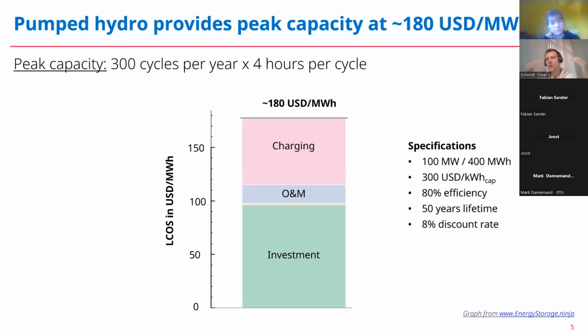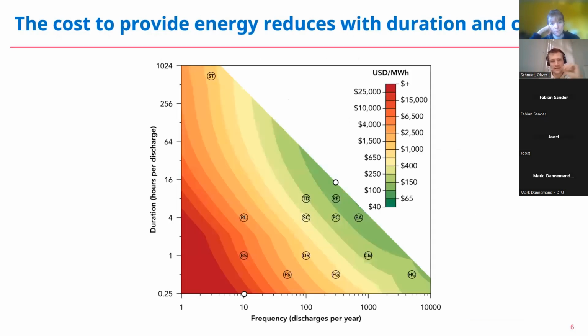Now, I would like to do this for all possible applications there are, and I'm going to do that on the next slide. On the next slide, you can see on the y-axis the discharge duration of any possible application, ranging from below 1 hour up to 1,000 hours. And on the x-axis, the annual cycles of any possible application, ranging from 1 cycle per year up to 10,000 cycles a year. So if we orient ourselves again, we were looking at peak capacity on the slide before, which had 4 hours discharge duration, 300 cycles. So it's sitting here. And we see we are in the range of $150 to $250 per megawatt hour. On the previous slide, we were in that range with $180 per megawatt hour.